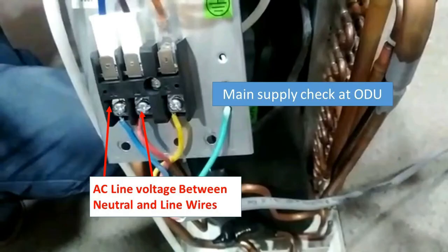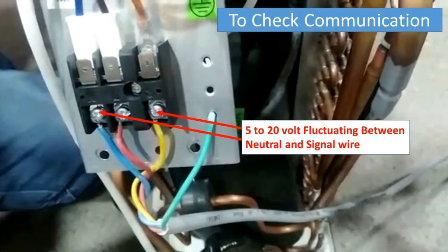So for checking the ODU, put on the AC, check the supply between line and neutral wire. It has to be line voltage. For checking the communication, we have to check the DC voltage between neutral and signal wire. If it is fluctuating between 5 to 20 volt, the communication is okay, and if the voltage is not available, then the problem is in the indoor unit. And if we are getting a fixed voltage, not fluctuating, then the problem is in the ODU PCB.